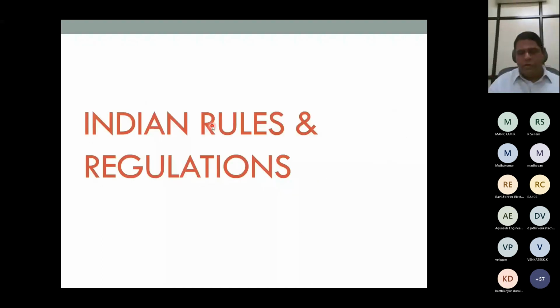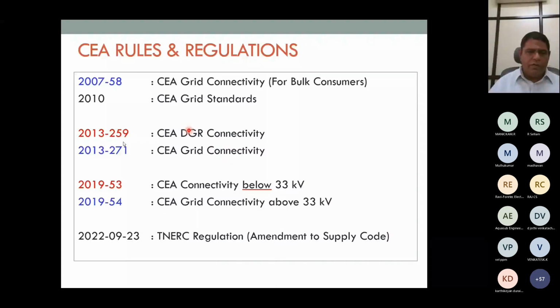So what are all the Indian rules and regulations? These are the Indian rules and regulations. 2007 onwards, the regulations have come. And again in 2010, then 2013. The current regulations are 2019-53, which is for below 33 kV consumers, and 2019-54 is for the above 33 kV consumers. And on September 23rd last year, TNERC has given an amendment to the supply code where all the consumers, HT consumers, are obligated to control the harmonics.